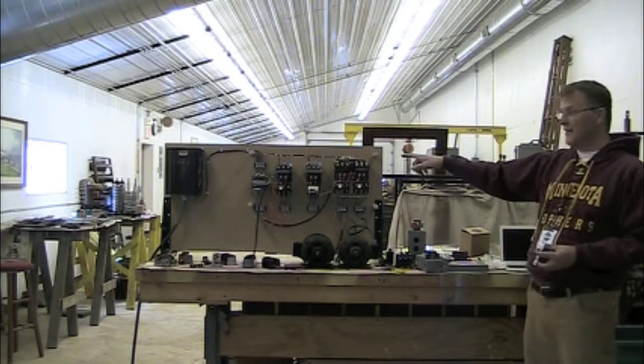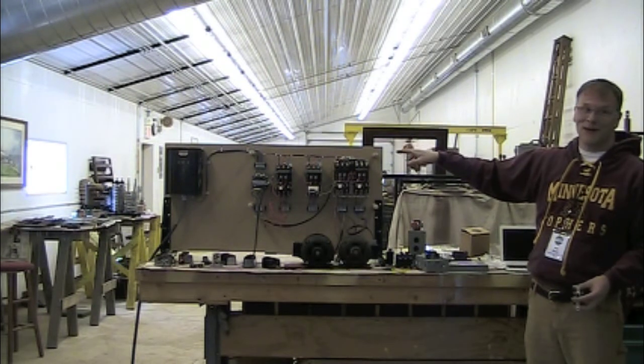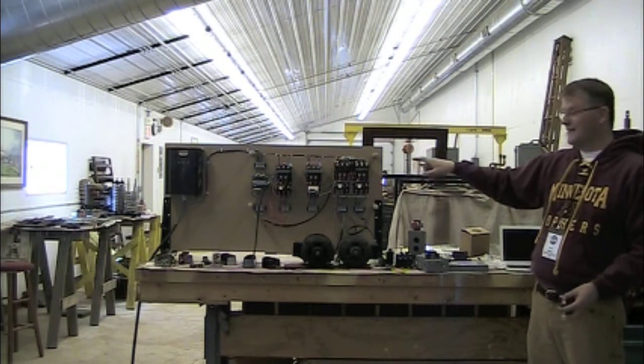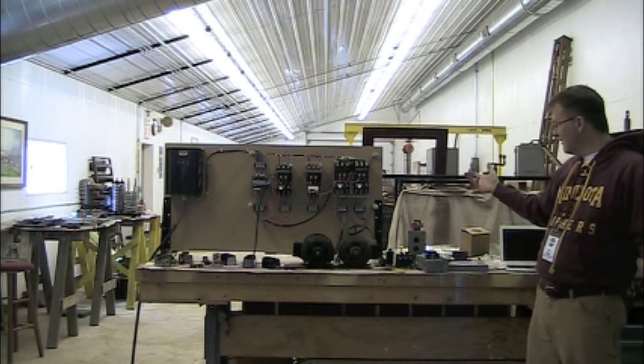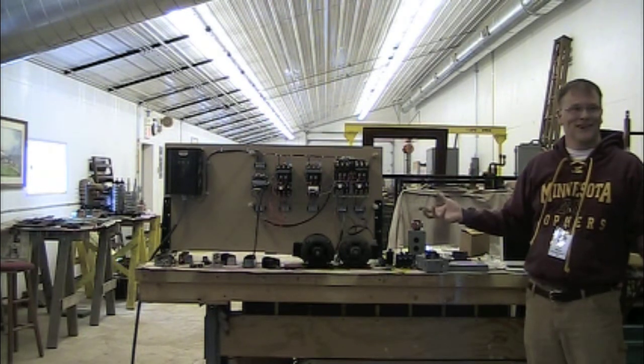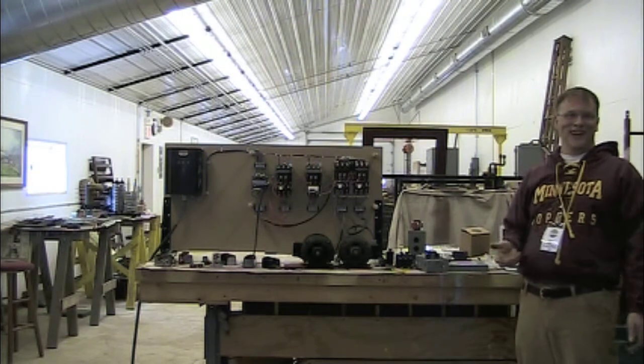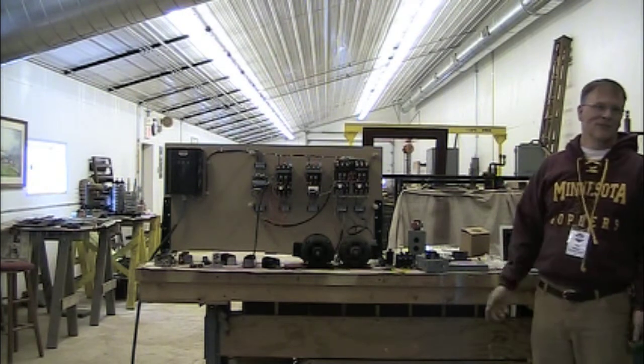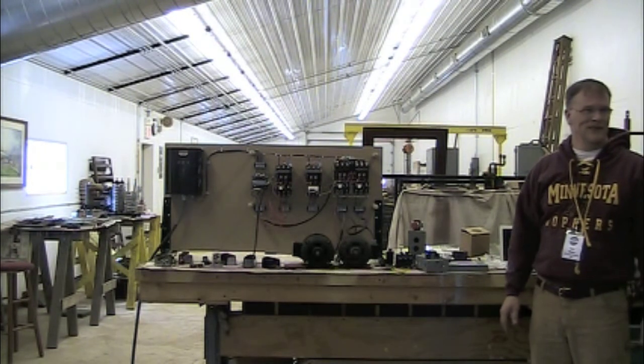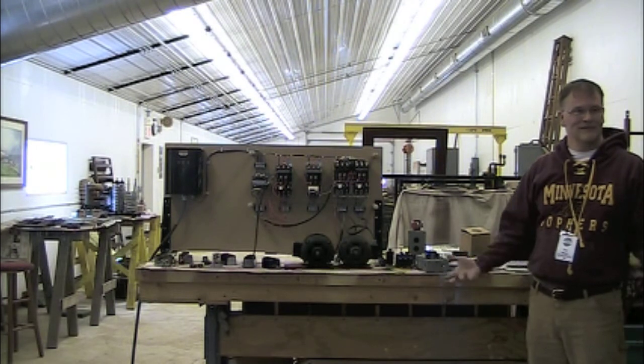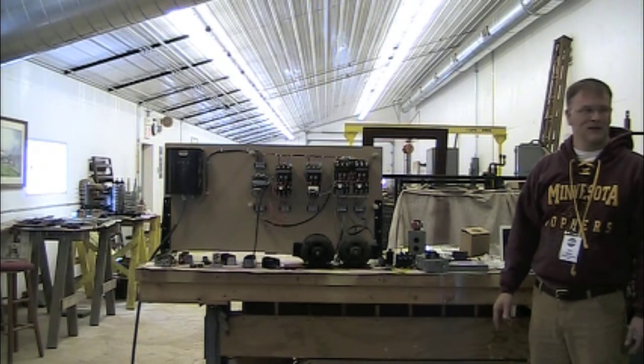Like I did on this. It would have been good for the demo. I wouldn't have wanted it to happen, but I'm running, and all of a sudden the motor wasn't turning. It was like the motor yesterday, it wouldn't start. And boom, the overload relay tripped, because it was trying to start, it wouldn't go, and it did exactly what it was supposed to because I lost a phase.